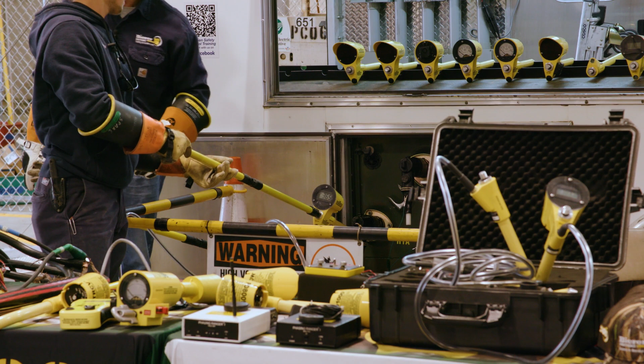Okay, go ahead to the next capacitive test point, the upper one. There you go. What do you get? 279. Okay, so we got a difference of about 100 volts, more or less, give or take. So if we're phasing and we're in phase, what we're going to see is the difference. We're going to see close to the 100 volts. Do the subtraction, and that's where you get down to zero, the difference.